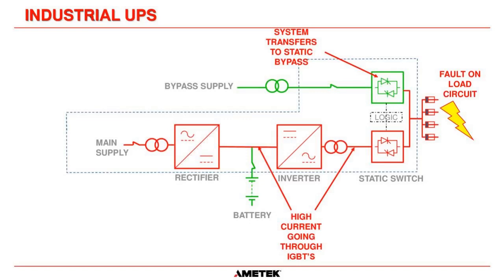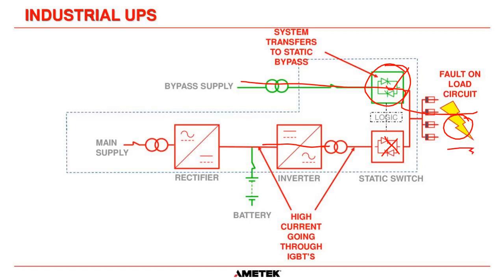The other reason we transfer to bypass during a load fault is that the inverter doesn't have enough stored energy to clear the fault. But bypass is fed from a robust transformer with more than enough power to clear the fault. Once the fault is cleared, the system can transfer back to inverter if auto-retransfer is turned on. If we have a fault on the load circuit, high current through the inverter bridge could damage the IGBTs, so the UPS turns on the bypass static switch to clear the fault while disconnecting the inverter static switch.